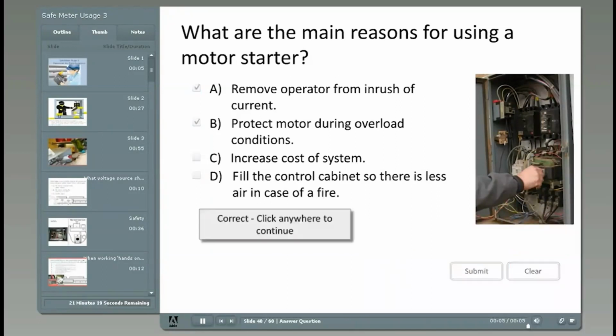The correct answers are A, remove the operator from the inrush of current, and B, protect the motor during overload conditions. Several reasons. One reason is to remove the operator far from the inrush of current. If a 480-volt power problem develops in the circuit, the wiring to the motor, the starter breaker is designed to take the heat within reason. The starter overload trips when the motor works too hard, or the breaker trips when the motor or wiring shorts to ground or shorts phase to phase. Sometimes when a short happens, the breaker's interrupting capacity is not high enough, and the breaker or starter blows up like a bomb.